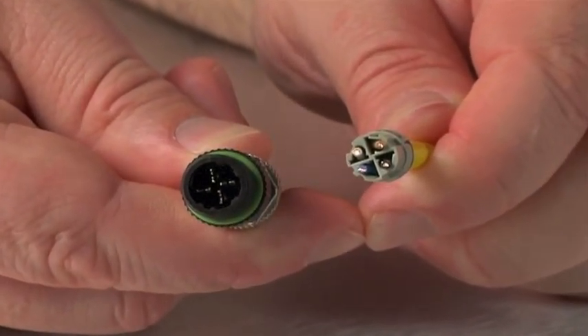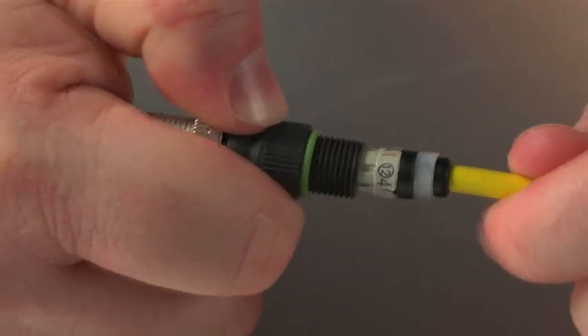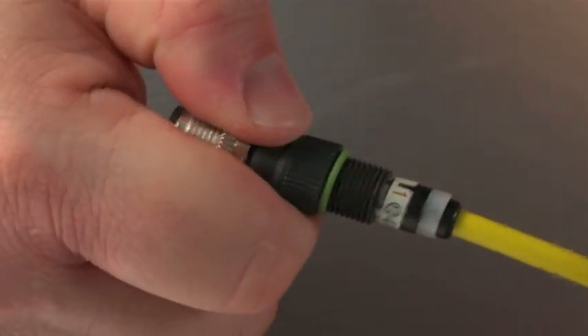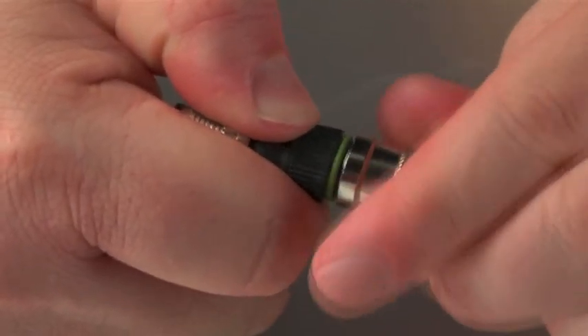Align the contact carrier with the connector termination. Alignment keys are present to help with this step and to prevent improper pin alignment. Press the contact carrier and strain relief into the back of the connector termination.